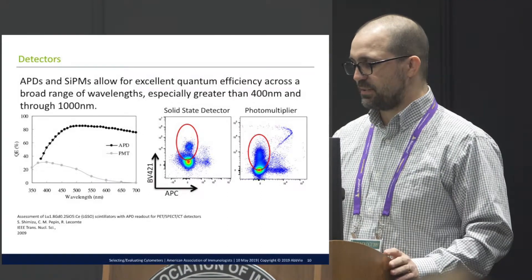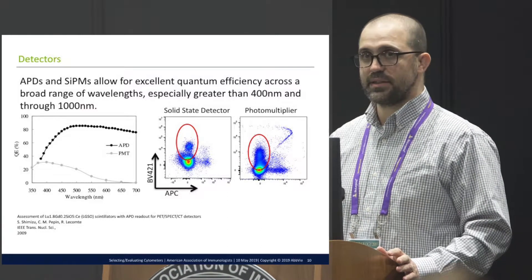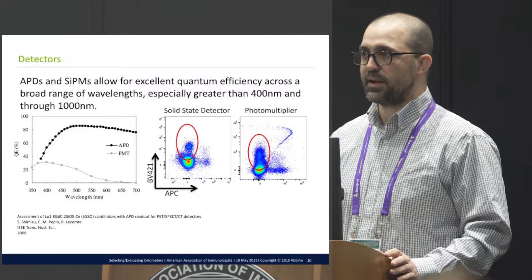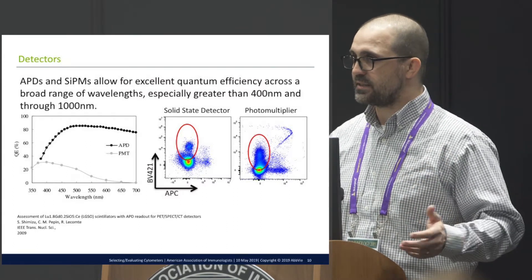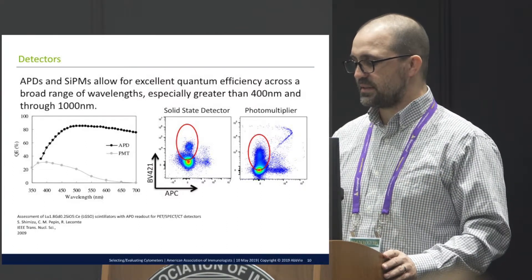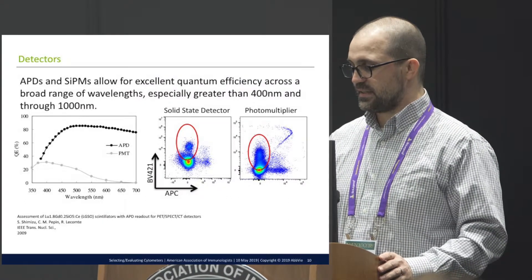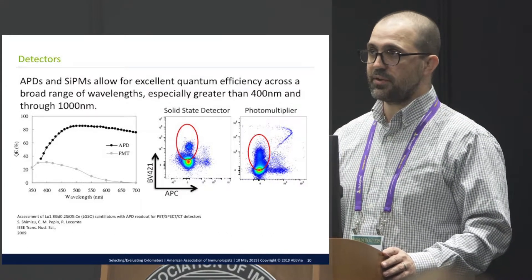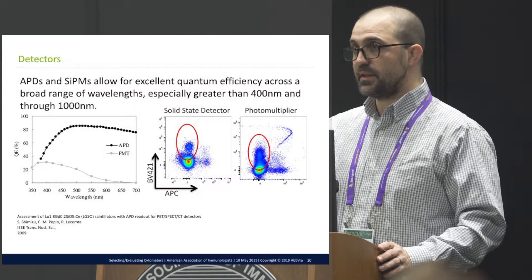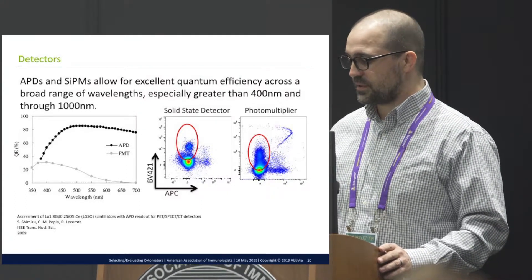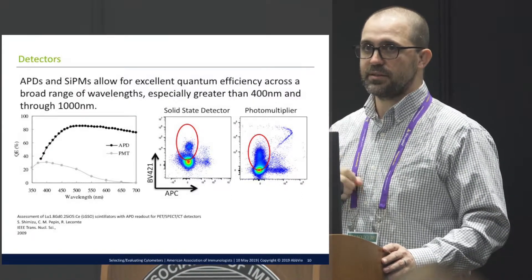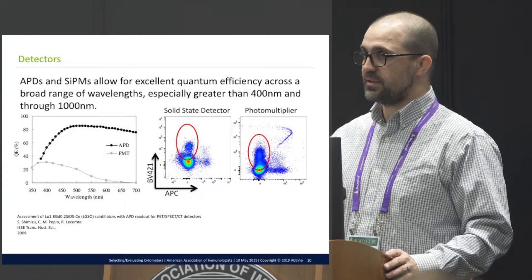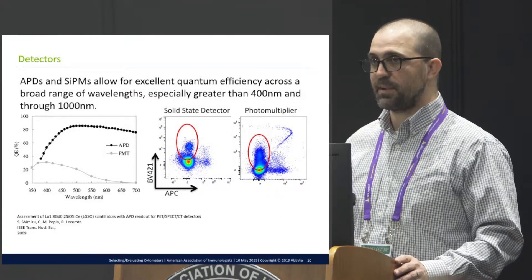This is a sample collected on an instrument that uses solid-state detectors versus one that uses photomultipliers. It's not a totally fair comparison because the instruments also have different laser powers and filters. But in general, what we typically see is tighter resolution of the negative cells and better resolution of DIM positives. Switching to solid-state photodiode-type detectors seems to have a better impact on collecting low amounts of photons from very dim signals, still giving good resolution and detection of populations.